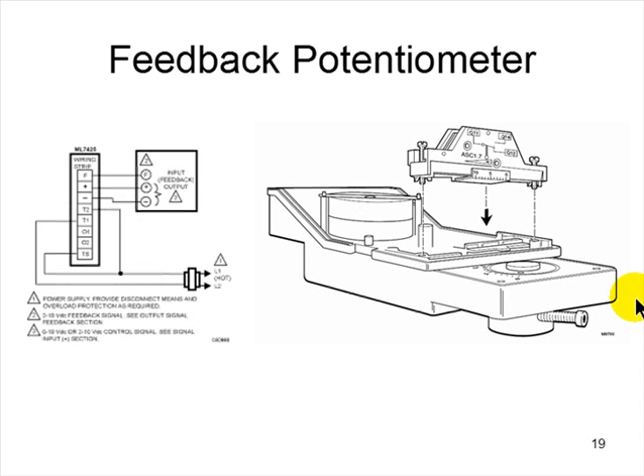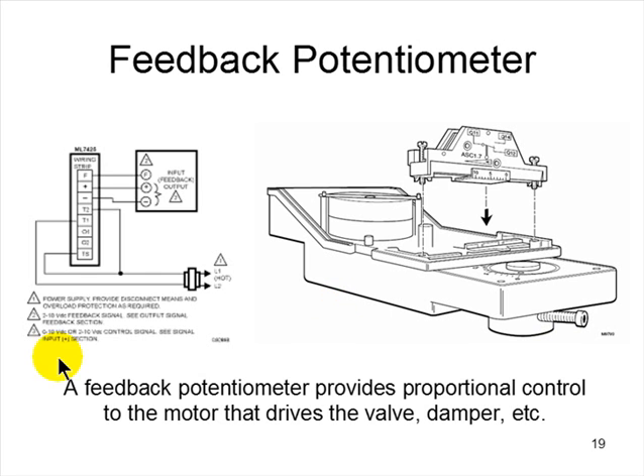Feedback potentiometer, very quickly. I don't want to beat this to death, but that's what one physically looks like, if you will, that attaches to the motor. A feedback potentiometer provides proportional control, which is the key phrase here. Proportional control to the device, the motor that drives the valve or the damper, the steam valve, the hot water valve, whatever the case is. Let's say you've got a hot water heating system in a commercial building, and you've got an open-close valve, what they call a 2-position valve. It's either wide open or completely closed. There's no in-between. A feedback potentiometer gives you in-between.